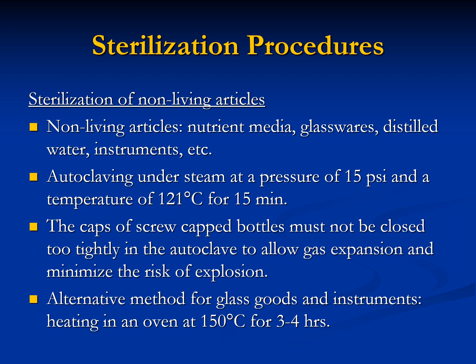It should be noted that when autoclaving screw-cap bottles, the caps must not be closed too tightly in the autoclave so that gases can expand without the risk of explosion. An alternative method of sterilizing glass goods and instruments is by heating in an oven at 150 degrees Celsius for 3 to 4 hours.